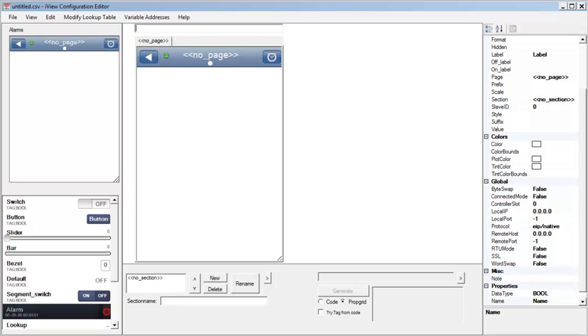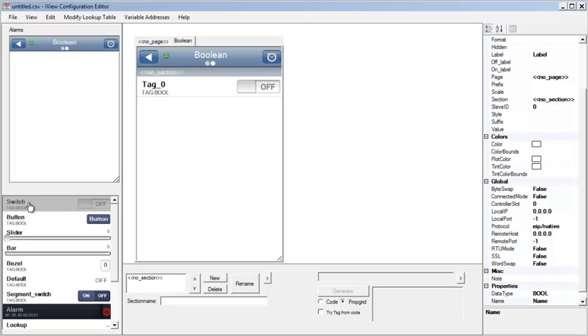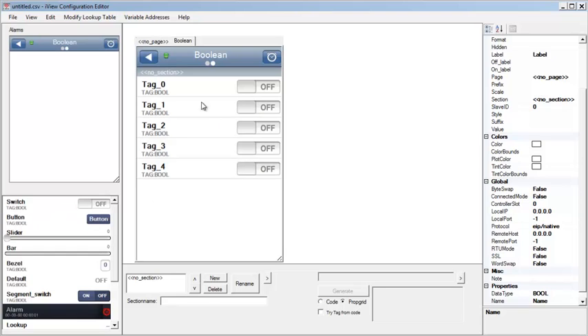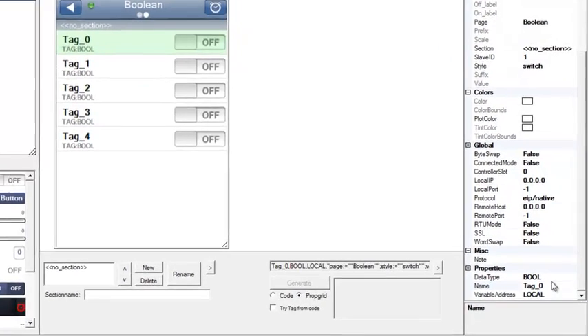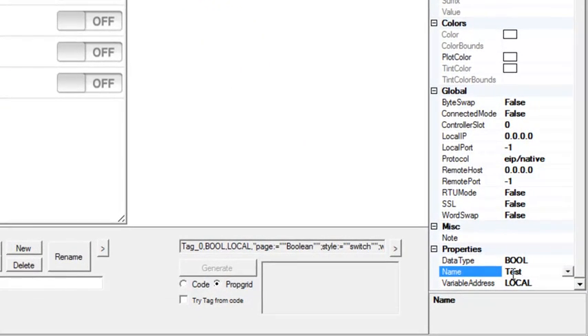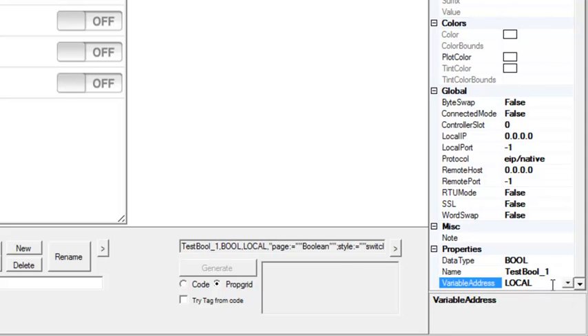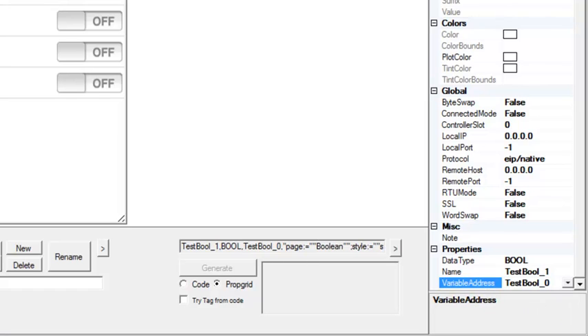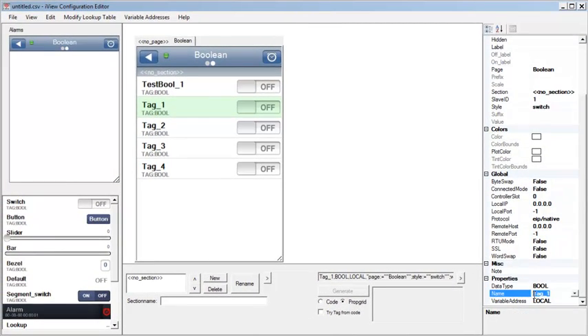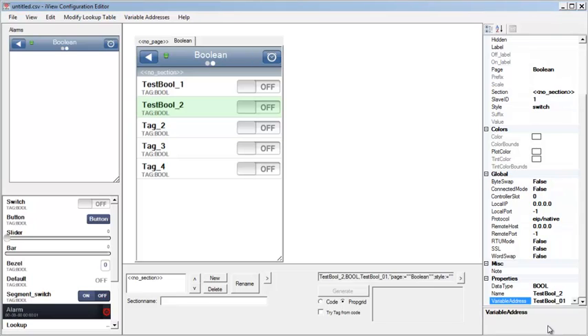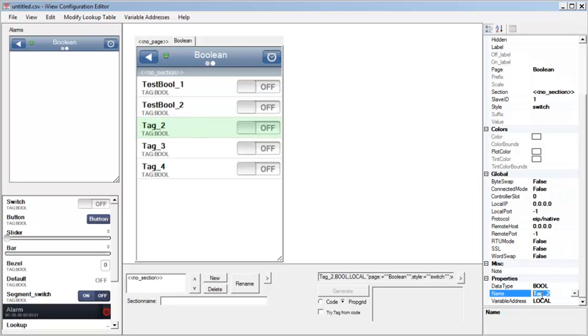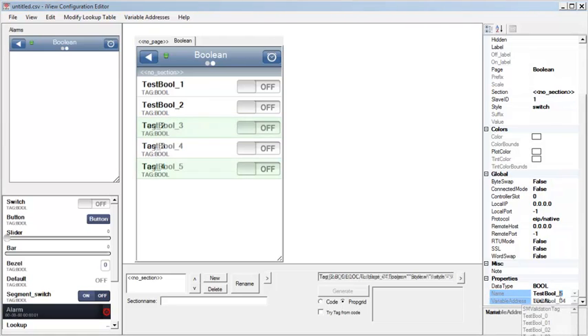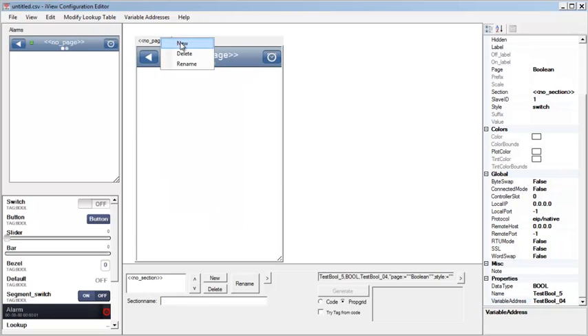Now I'll create a page for the iView interface. Right click on the No Page tab and select New. Give the page a name and hit Enter on the keyboard. I'll add the tags from the CSV file that I imported. I'll add five switches to my page by left-clicking on the switch tag in the Tag Selection toolbar. I'll select the first tag and look at the bottom of the Items Properties window. I'll give the tag a name by clicking on the Name field and entering a name. Next, I'll click on the Variable Address field and use the drop-down menu to select the TestBool underscore zero tag from the CSV file. This is the process for linking the controls that you place on your page for iView. Now the first switch tag in the iView page is linked to the TestBool zero tag from RSLogix 5000. I'll use the same technique to link all the other TestBool tags.